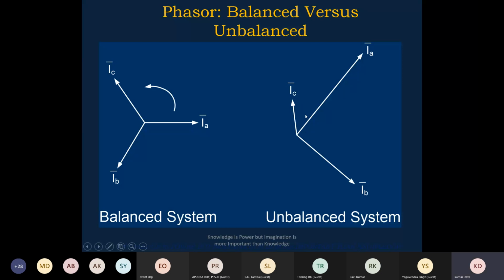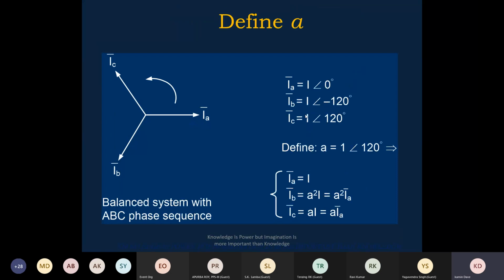Normally fault conditions, motor start, transformer charging, capacitor charging, and cable charging, when it is a long cable and we close the breaker, give a waveform that is not symmetrical. Those phenomena are unbalanced systems. A motor running under an unbalanced condition, like load jamming, is also unbalanced.